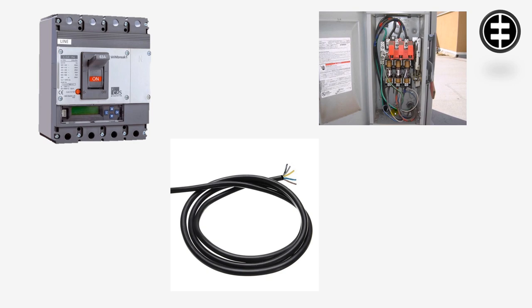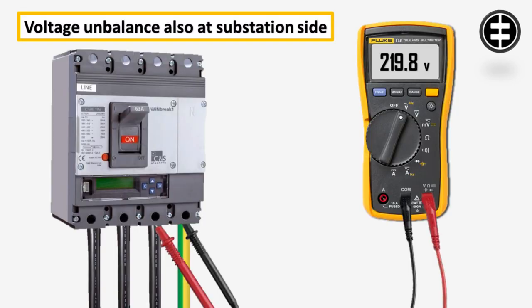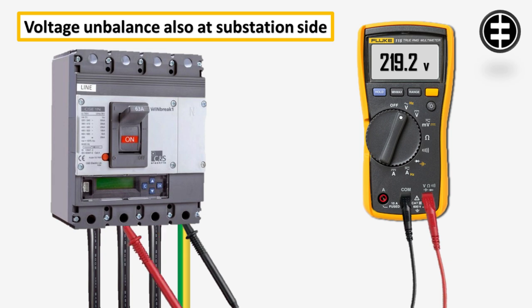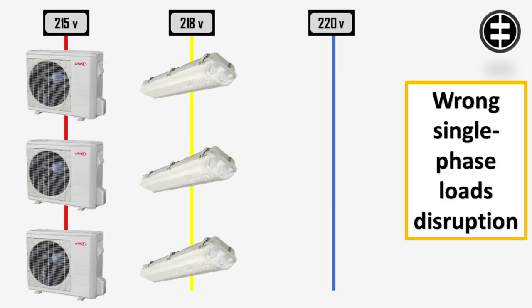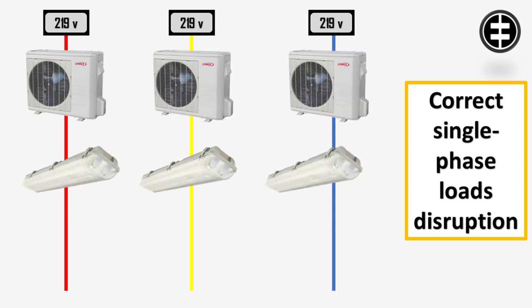If the voltage unbalance was also at the substation side, you need to check the load unbalance. Normally in three-phase systems, the single-phase loads such as lighting, air conditioners, etc., must all be properly distributed between the three phases to avoid increasing the load on one phase. Load unbalance will lead to voltage unbalance.